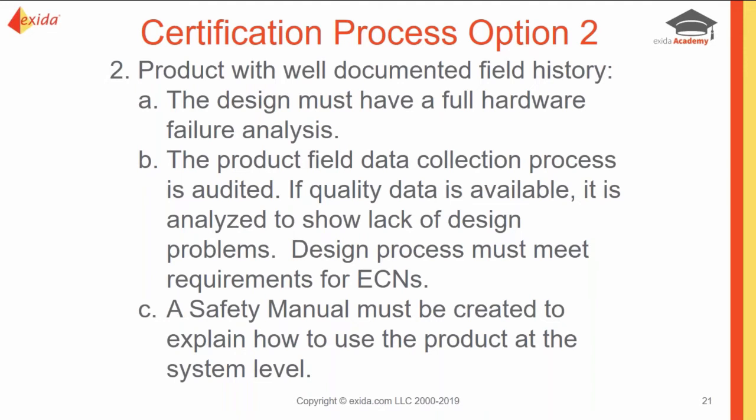So this is great if you have a fully compliant design process and maybe a product that has maybe 3 or 5 years at least history. This option is going to rely more on your proven in use assessment. And because of that, we don't need to rely as heavily on verification or validation documents. This is great if you have an older product that really hasn't changed much in the past so many years. Example, valves. Some valves really haven't changed in the last 5–10 years. And you may have a great record-keeping system, and you might have the ability to take away a few of those requirements.